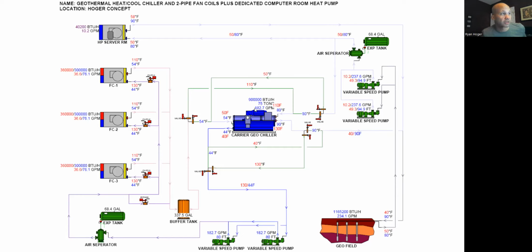On the other side of the chiller, I have these other water loops, which has its own pumping system and its own air separating expansion tank, because this water loop doesn't touch this water loop, right? At least not initially. And then I send that down to the geofield. Instead of having reversing valves in the chiller, before we had those kind of chillers, we could put reversing valves on the water. It's not as easy. Instead of 1 reversing valve in the refrigerant pipe, I needed 1, 2, 3, 4 on the water valves.